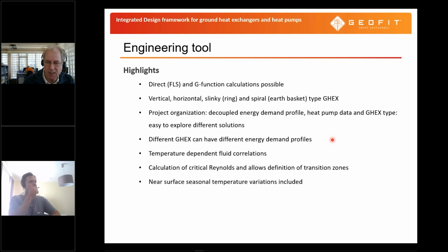And then, of course, you cannot easily do that with a G function approach, but you have to use perhaps the direct FLS calculation to get that solution. We have vertical, horizontal, ring, and spiral type heat exchangers. We have taken care of project organization. Like I explained, we've decoupled the energy demand profile, the heat pump data, and the ground heat exchangers type so that it is easy to switch between them.